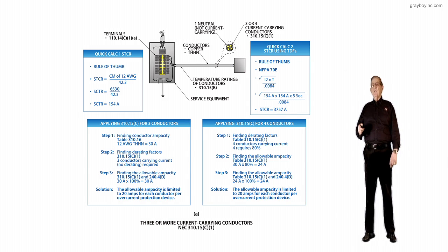We went through the section you'd look at. So you have to apply an 80% de-rate factor. So 80% of 30, you come up with 24. That is still enough amps to supply a 20-amp circuit at 24.